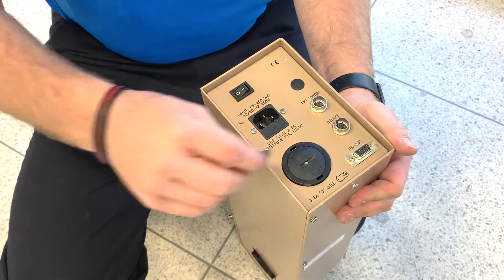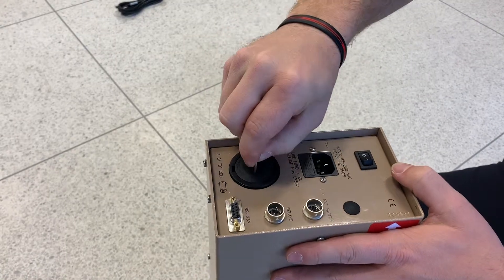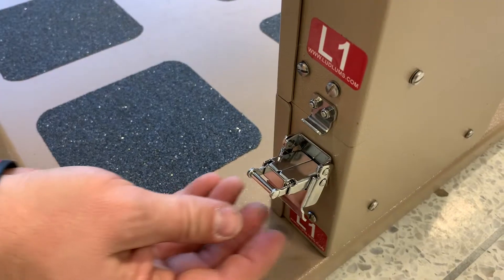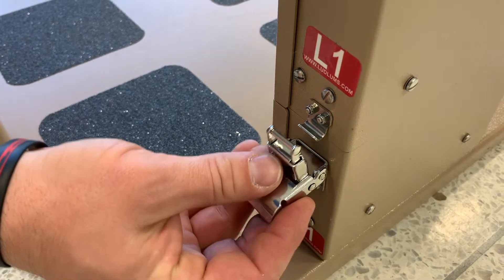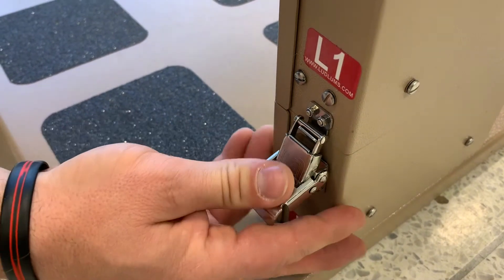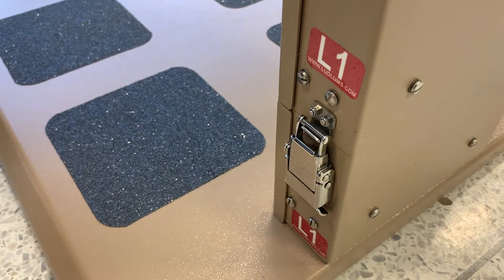The portal monitor can be assembled without tools, but the use of a quarter can be helpful when installing the batteries. All connections are made with latches. To connect the latch, lift up the bottom tab, hook the top cross bar into the hook on the piece that you are attaching, and push the tab back down until it snaps into place.